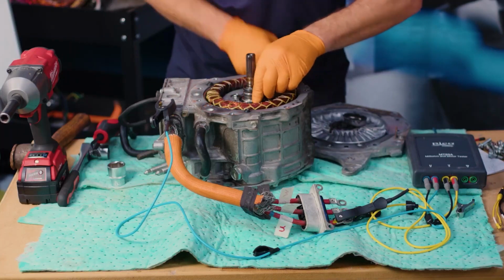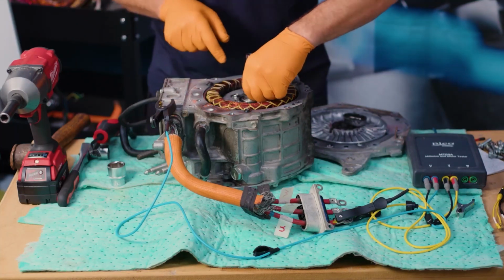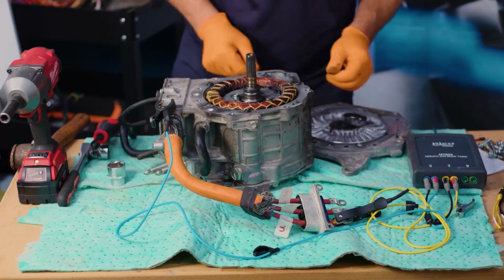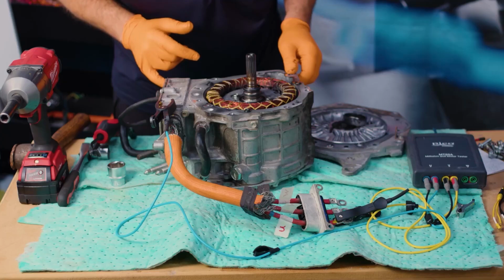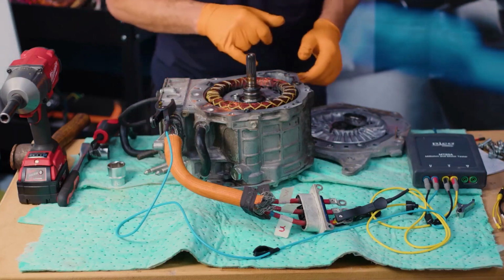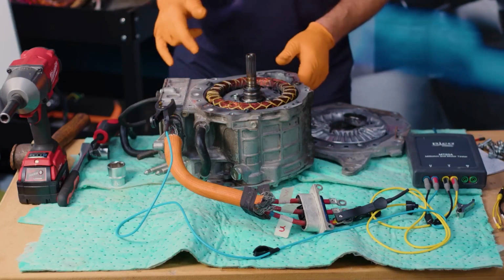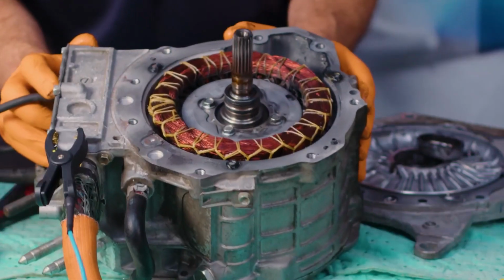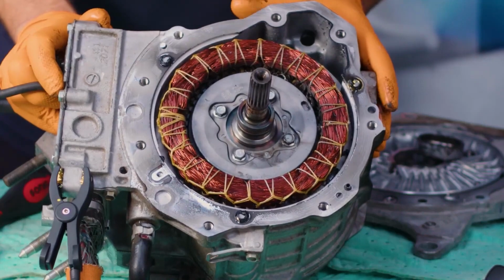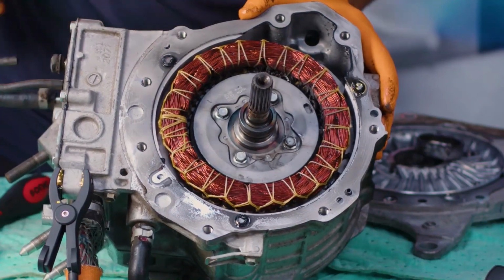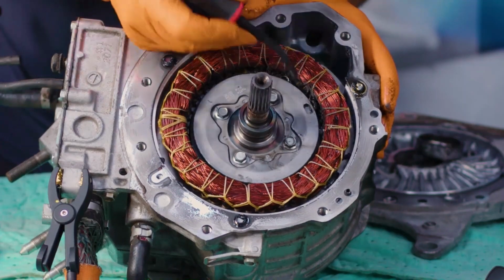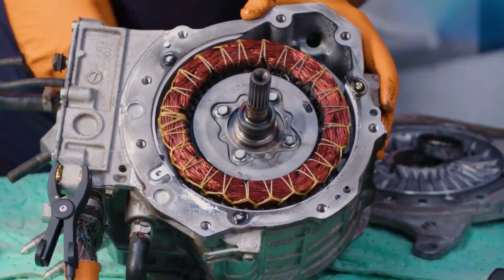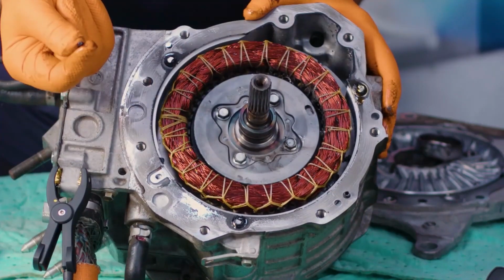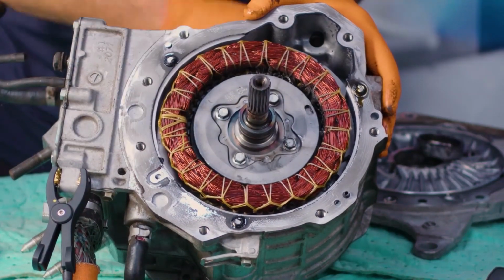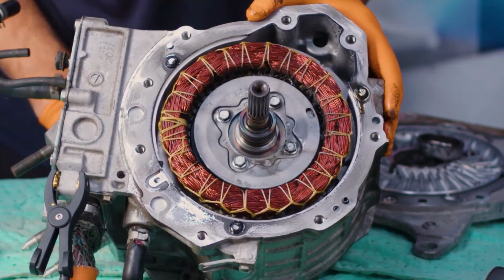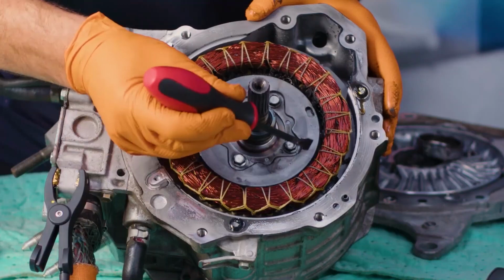It does look as though this has got hot, looking at the discoloration on the inner race of the bearing. There is also, oh, that's very interesting. There looks to be debris. I don't know whether we can bring the camera in here, or maybe if I turn this over, we see. We're at 60 milliohms still. And this is what I'm concerned about, is this here. So, fragments of metal, not sure where that is from. Most likely the bearing, maybe the carrier. Yeah, there's discoloration around here.